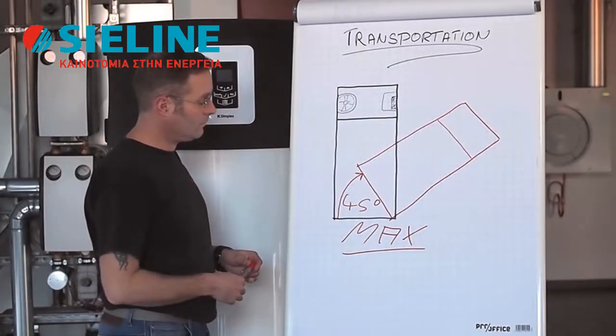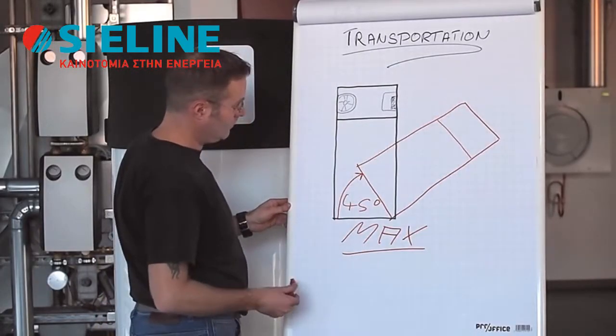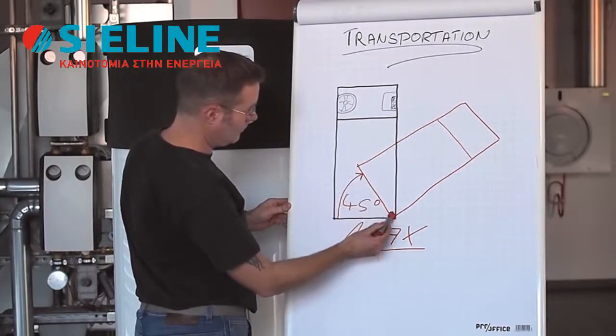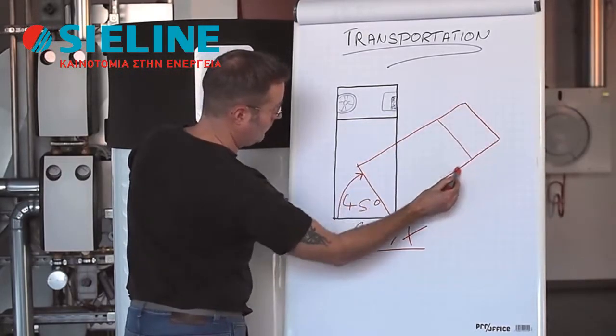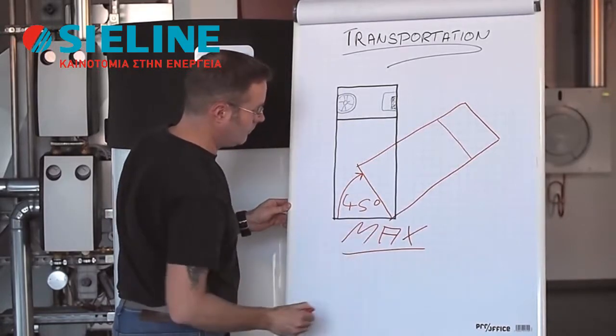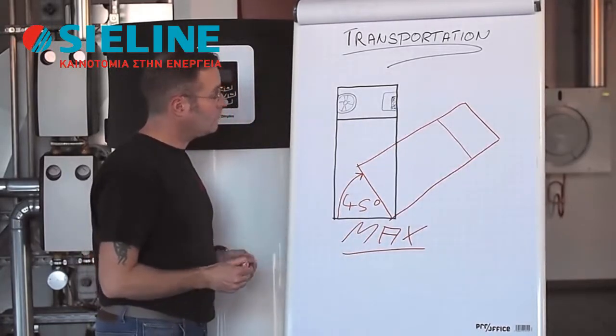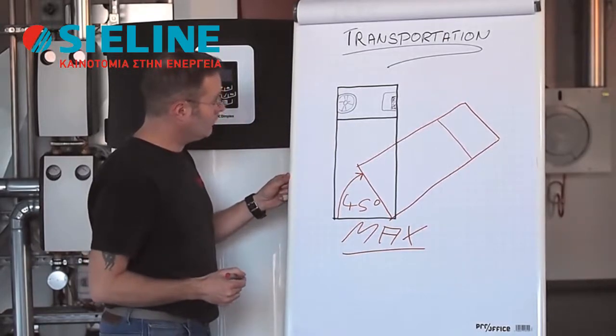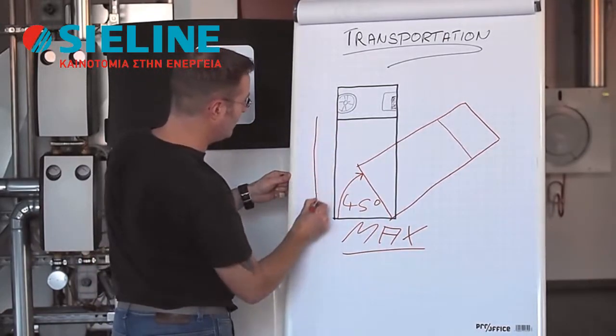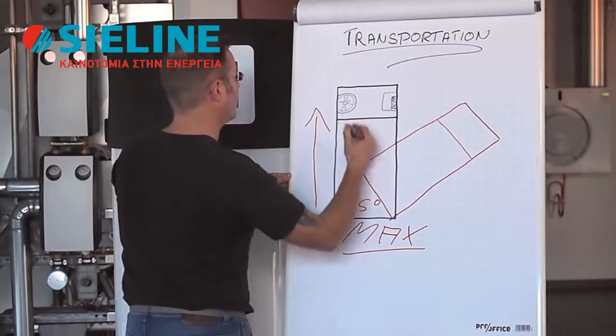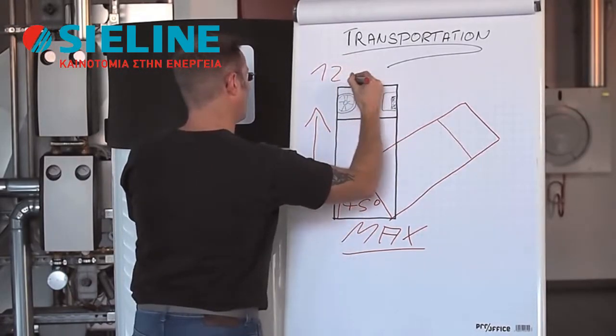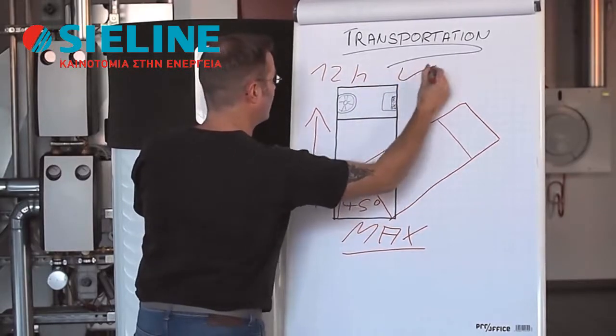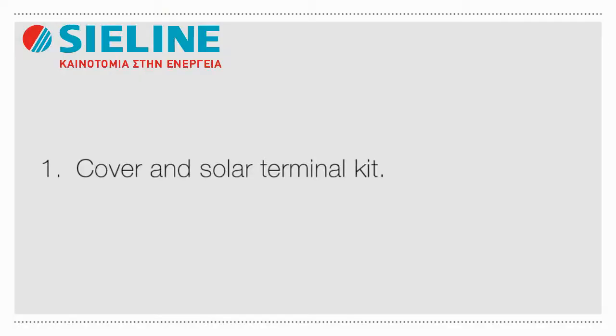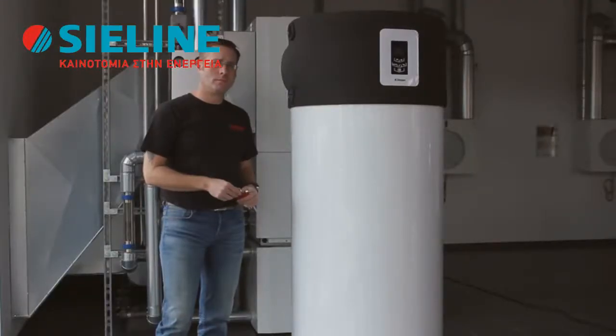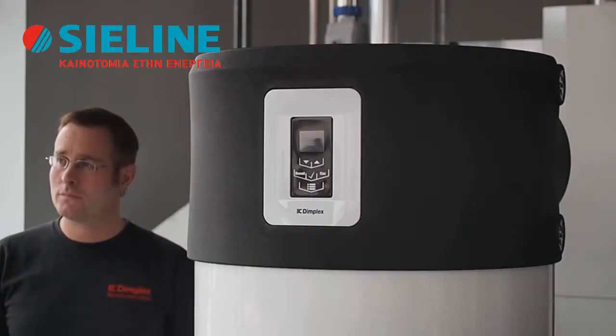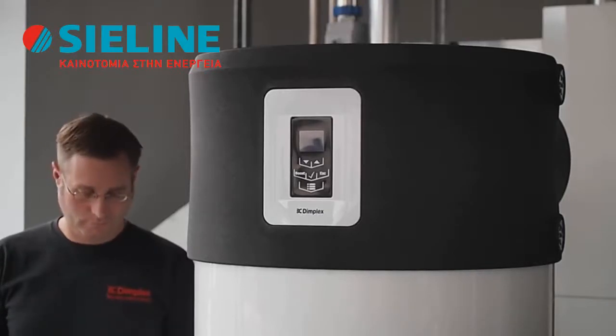When transporting the heat pump, do not, under any circumstances, exceed the maximum tilt angle of 45 degrees. After any transportation, keep the heat pump in an upright position for at least 12 hours before you start the compressor. After the heat pump has been brought to its installation location, you have to open the device.